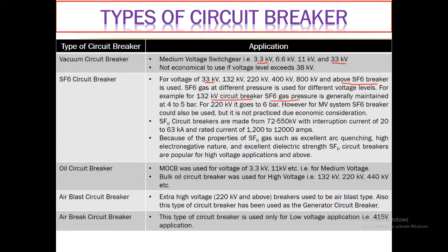For SF6 circuit breakers, considering the properties of SF6 gas, they are quite useful where the voltage level is very large. For example, for a 132 kV circuit breaker the SF6 gas pressure is generally maintained at 4 to 5 bar; for 220 kV it goes to 6 bar. SF6 circuit breakers are made for 72 to 550 kV with interrupting current of 20 to 63 kA and rated current of 1200 to 12,000 amperes.